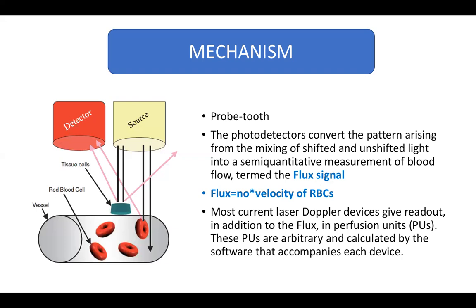The flux is a measure of the number of red blood cells and their velocity. Most current laser Doppler flowmeters also give a readout in perfusion units, which are arbitrary and calculated by the software of a particular device. Hence, different devices give different perfusion units and they cannot be compared.